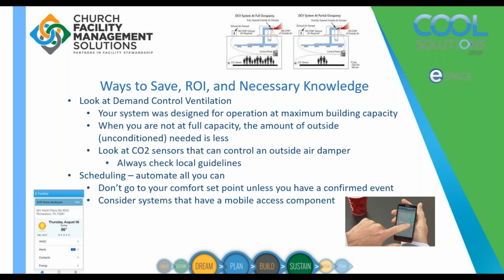A lot of time you can monitor that through CO2 sensors. We can monitor it in the most occupied spaces, and that's where it's always recommended to put those CO2 sensors. As long as it doesn't exceed 1,000 parts per million, which is a general rule, then don't bring in outside air, because what is outside air? It's unconditioned air. So if it's 100 degrees outside and you're trying to cool to 72, bringing in 100% of the volume of outside air that the system is designed for means you're trying to cool this 100-degree air down to 72, rather than cooling your building air of 78 down to 72.